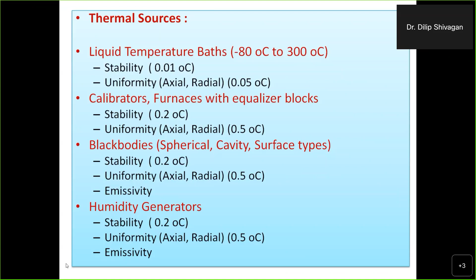It should cover all the range, and you should be able to convert from that EMF uncertainty to degree Celsius uncertainty. Similarly, drift, sensitivity and environmental factors need to be carefully assessed. A direct temperature indicator, if you are using one that reads temperature directly, is a little poorer, because when we measure the direct property, resistance or EMF, your level of uncertainties is very good. When you convert further, your level of uncertainties will increase. So you need to characterize them from the electrical section, and if you have the coefficients available from the prior calibration, you put them in after the present calibration, and then you can read very accurately.